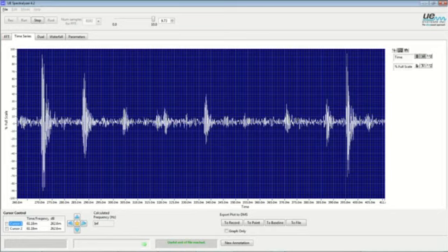That spacing being different tells us those discharges are taking place at different points in time in a very random fashion. That is characteristic of a tracking event.